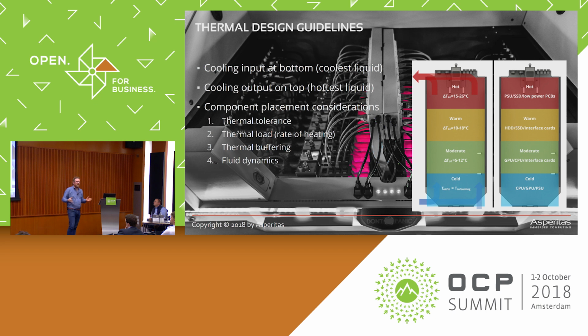Another property of any open bath immersion system is that gravity will always try to separate the thermal layers. That means the bottom of any immersion tank, whether it's 3M Novec, oil, or any other open bath approach, will have the coolest liquid at the bottom, while the top layers will always be the warmest. That's something you can actually benefit from.